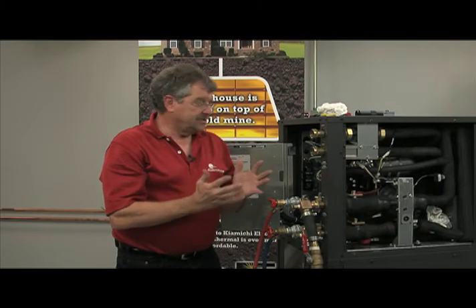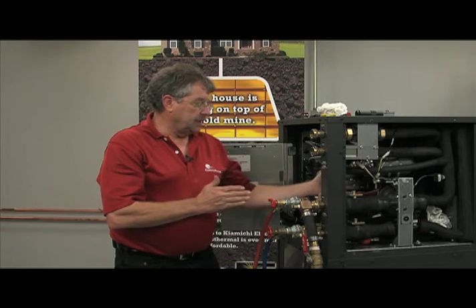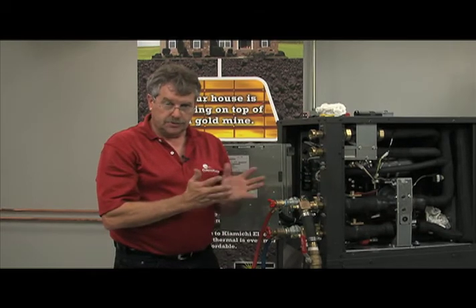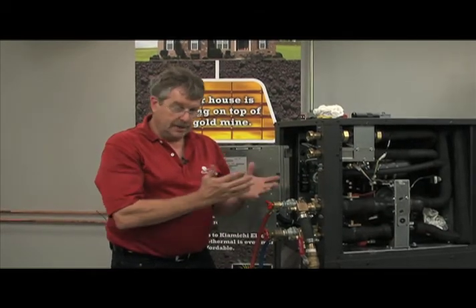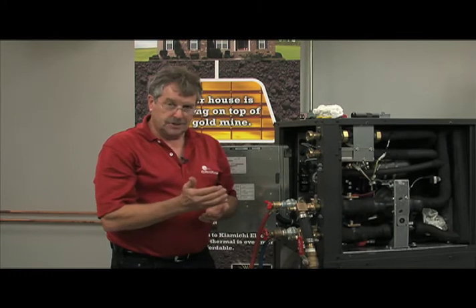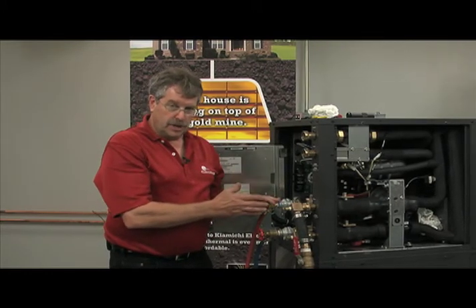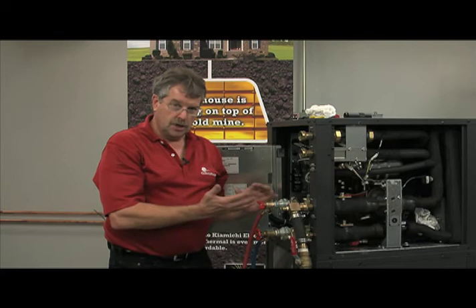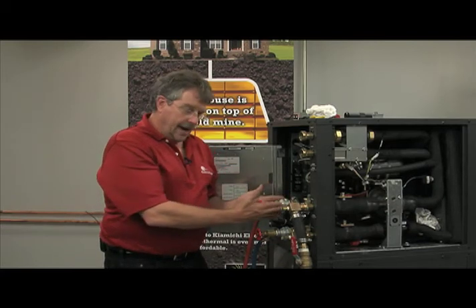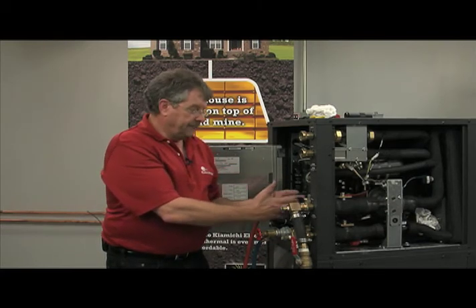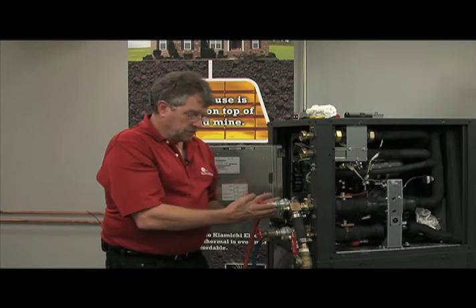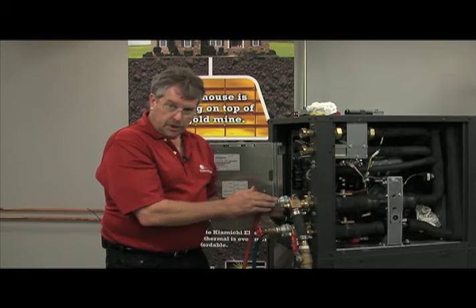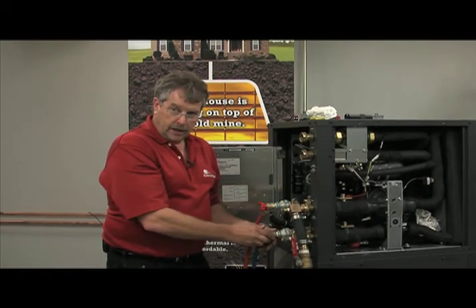So guys, that's some of the procedures you want to follow to address replacement of sensors. Again, if something showed up and compromised those sensors, this can be a fairly easy and painless way without dragging the flush cart, hoses, and all that apparatus in. Have a couple of hoses, have the ability to get from that 1-inch flush port to some kind of a boiler drain and control assembly, both on the outlet and on the inlet.